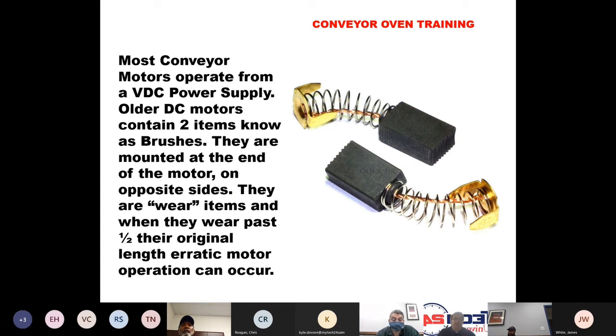Conveyor motors, especially older conveyor motors, operate on a DC power supply. The older DC motors contain two of these items that are called brushes. They mount at the end of the motor on opposite sides. They are a wear item. When they wear past about half of their original length, you might get erratic motor operation.